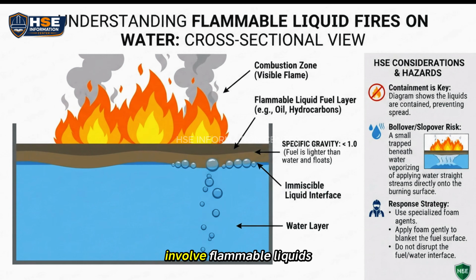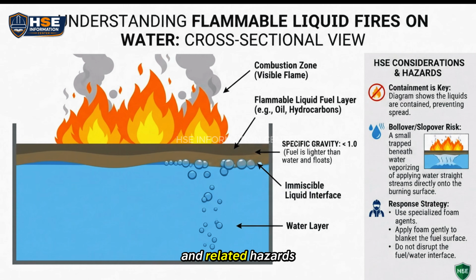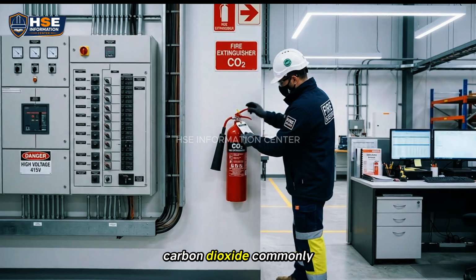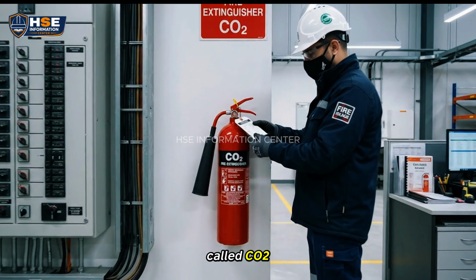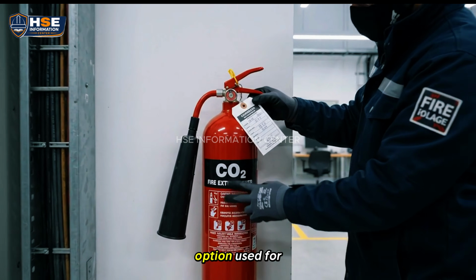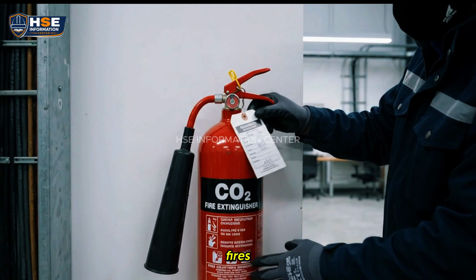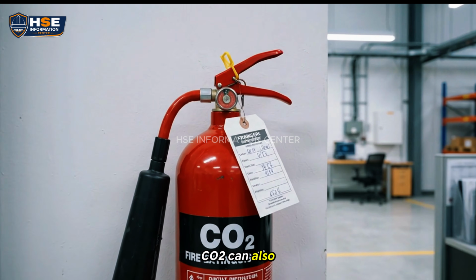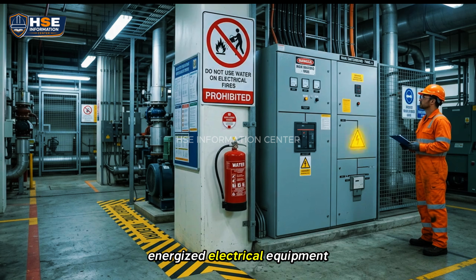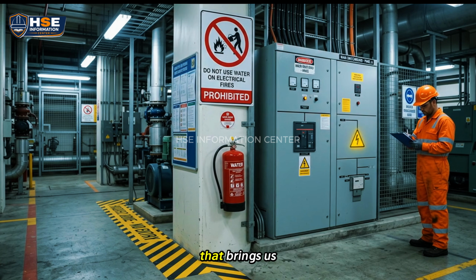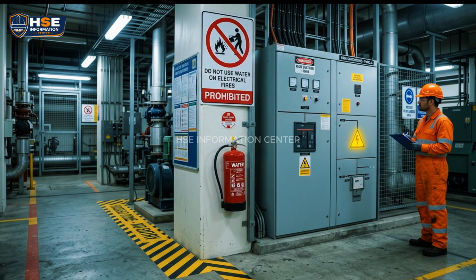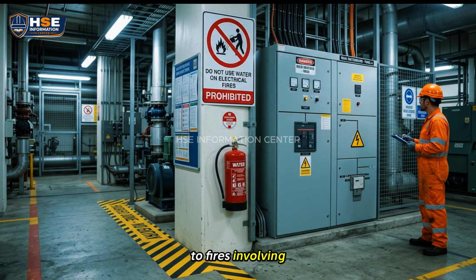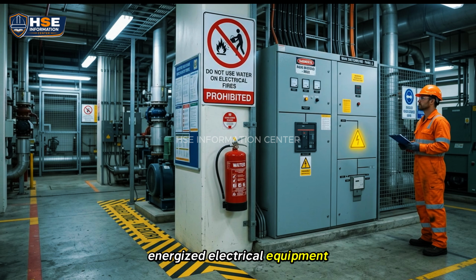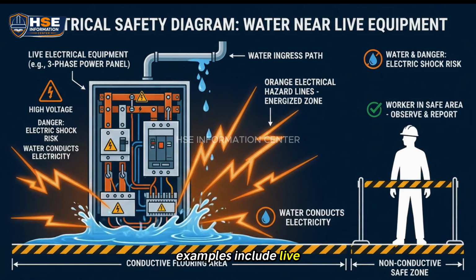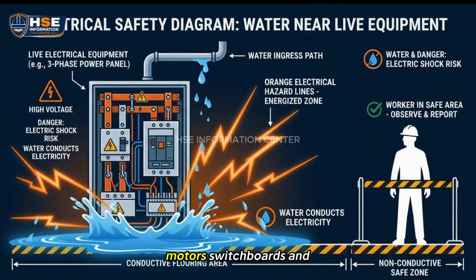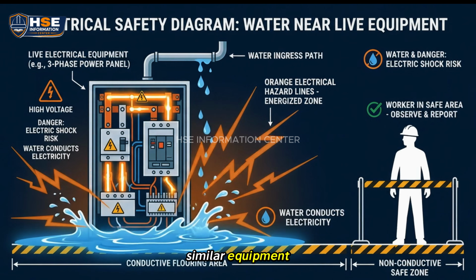Class B fires involve flammable liquids and related hazards. Carbon dioxide, commonly called CO2, is one extinguisher option used for certain Class B fires. CO2 can also be used where energized electrical equipment is involved. That brings us to Class C. Class C refers to fires involving energized electrical equipment. Examples include live electrical panels, motors, switchboards, and similar equipment.